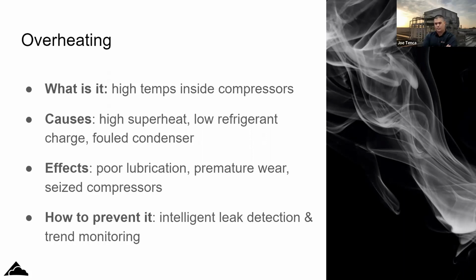as opposed to digging into it more, checking. Yeah, the condenser was dirty, but that's just what created the major problem. There's still an underlying problem. A dirty condenser shouldn't cause a compressor to stop running. That should just be something where you start running higher discharge and get some alarms on it. But if you have compressors tripping, or going off on oil because the oil's thinned out, or going off on demand cooling or overloads or tripping breakers, it's not a dirty condenser, but technicians are kind of limited in what they can do with contract accounts.